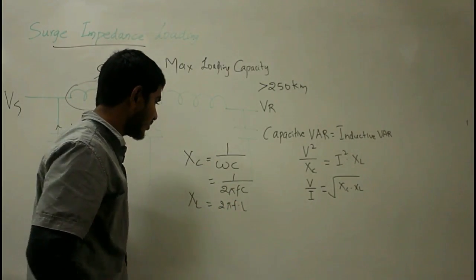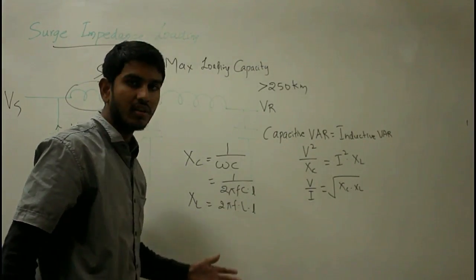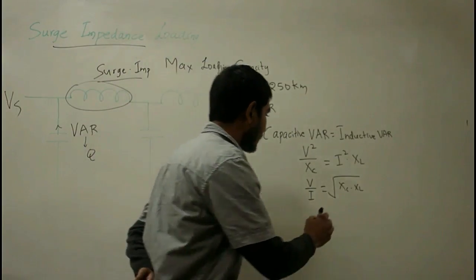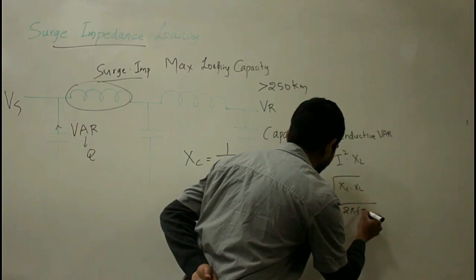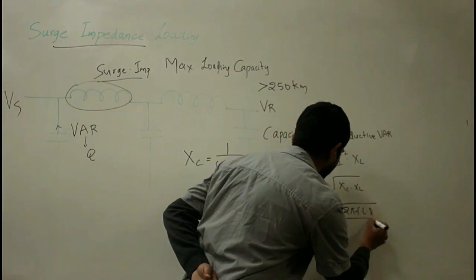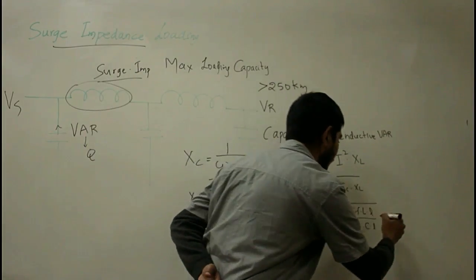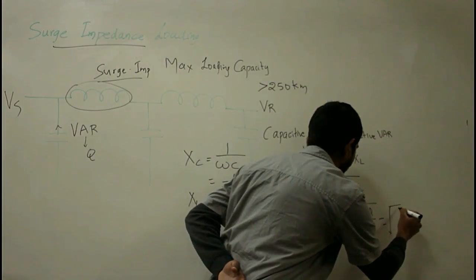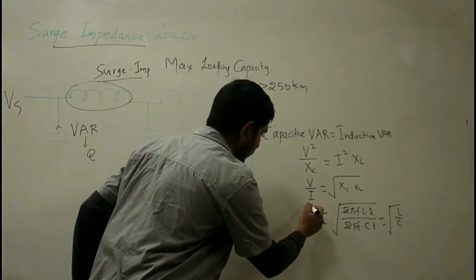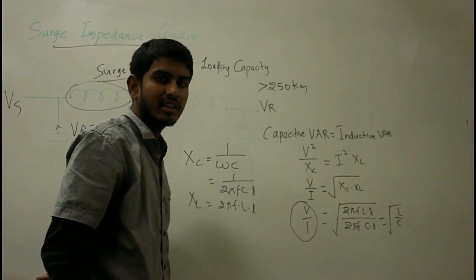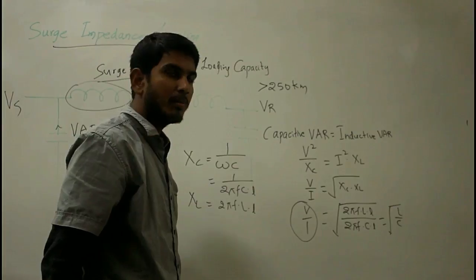If we consider per unit length, with L as the length of the transmission line, then XL = 2πF·L·l and Xc = 1/(2πF·C·l). From this we get V/I = √(L/C). This electrical quantity has the dimensions of electrical resistance and is your surge impedance, given by ZS.